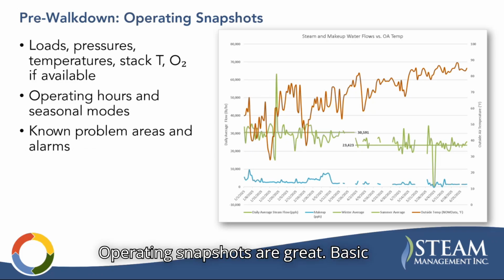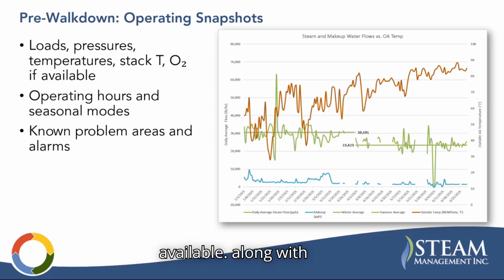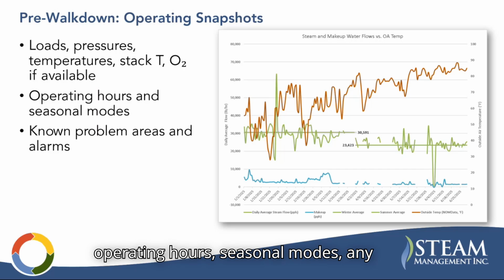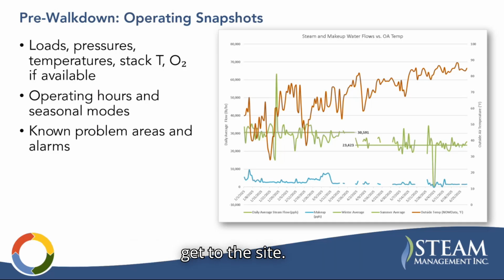Operating snapshots are great. Basic loads, pressures, temperatures, stack temps, O2 measurements if available, along with operating hours, seasonal modes, any known problem areas or alarms. It gives us a good picture of how the plant is currently operating, and maybe we can start putting together what opportunities may exist before we even get to the site.